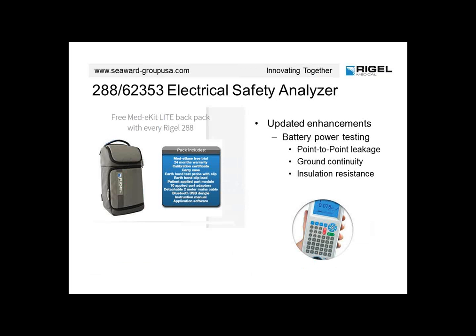The unit does come with a backpack style carrying case. As you see, a 2-year warranty, the applied part adapters and such. And to keep in line with what's new in test equipment, the 288 and the 62353 operate from internal batteries for stay alive function. And now you also can do your point-to-point leakage testing, ground continuity, and insulation resistance from the internal batteries.